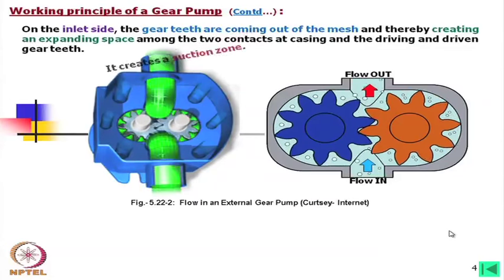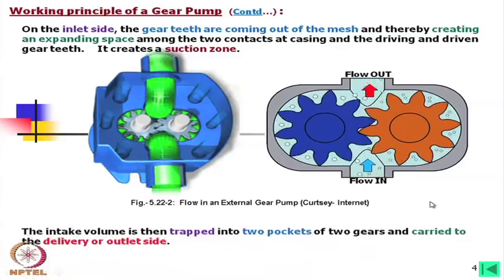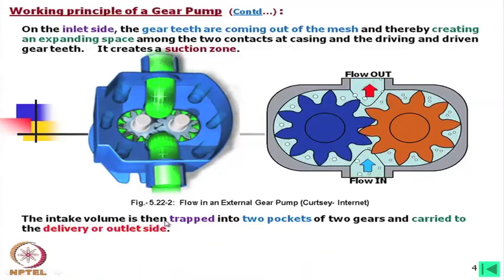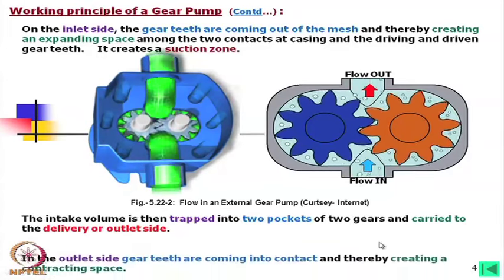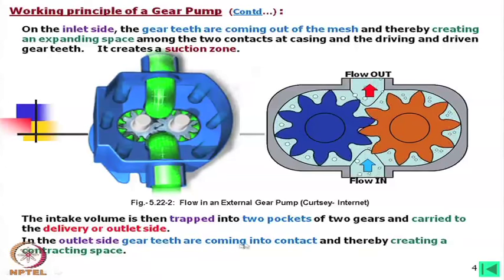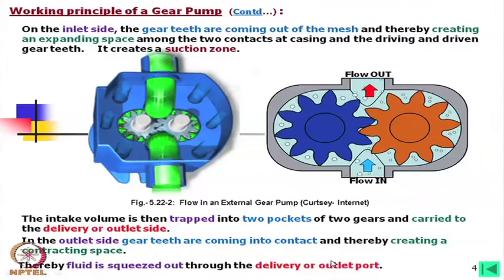It creates a suction zone on the inlet side. An intake volume is then trapped into two pockets — one pocket from each gear — and carried to the delivery or outlet side. On the outlet side, gear teeth are coming into contact, thereby creating a contracting space. Thereby, fluid is squeezed out through the delivery or outlet port. This is the pumping action in the case of a gear pump.